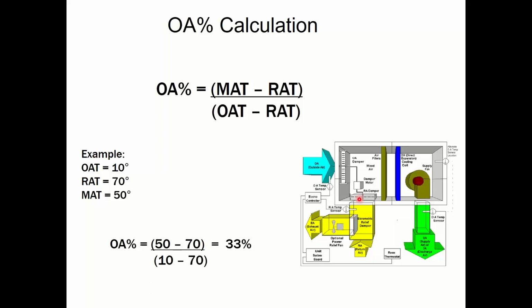If I know how much CFM that is, I'd have to know how much CFM the fan's moving. And if I don't know how much the fan's moving, which I might not, at a minimum, I could take an educated guess at the traditional 400 CFM per ton. If it's a 10-ton unit, that's 4,000. And if a third of that's coming from the outside, that's 1,300 CFM of fresh air. If my code only requires 1,000, that means I have 300 too much. I need to throttle my ventilation damper back and save some energy. And if it's too little, I need to open it up and provide better ventilation.